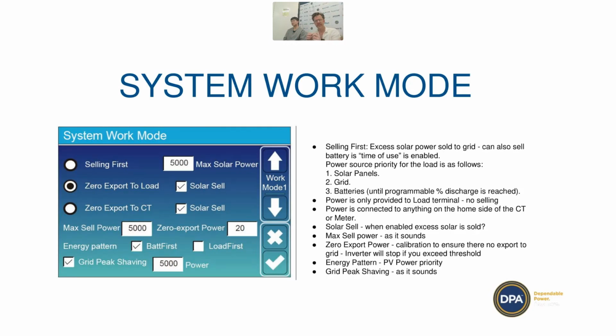But if you put the CT at the main switchboard and you've got a load in between the main switchboard and the inverter, then it will attempt to support those loads by exporting power out of its input terminals and then on, but not enough to push current out into the grid. The thing that's confusing about this is that it's either trying to keep the inverter itself current at zero and have nothing going out of the inverter, or it's trying to keep the meter or the CT at zero. It's probably the best way to describe that.